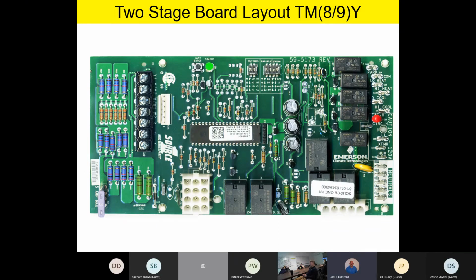If you'll take a look at the photo on the PowerPoint, you're going to notice on the left-hand side, you're going to have your terminal strip for your thermostat. So let's go over that one by one, just to make sure everybody's squared away. So starting at the top of the terminal strip, we see Y1. That'll be our first stage cooling call if we have a 2-stage piece of equipment outside. And by the way, let me take just a second or two as well on this. This is one of the most versatile furnaces we have in our inventory.